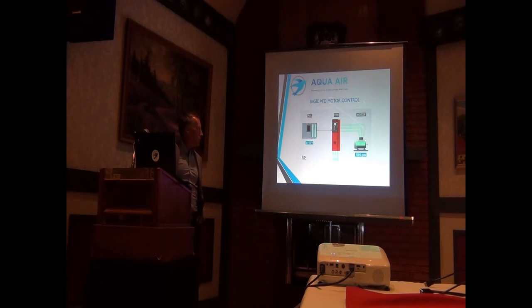Another big invention that helped efficiencies in the HVAC world was VFDs. Before the development of VFDs, in a lot of systems there was a set point, the system would come full on to meet set point, and when it met set point, full off. And with VFDs, VFD stands for variable frequency drive. VFDs are based on the demand of the system, and they vary your capacity to meet what the system is calling for.